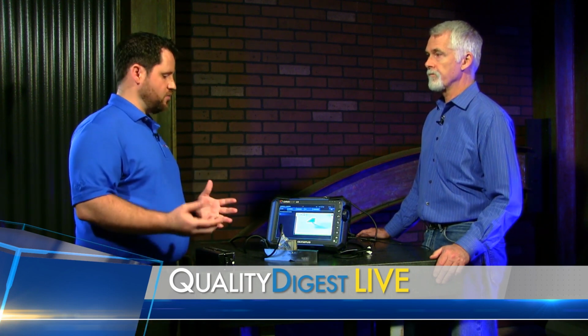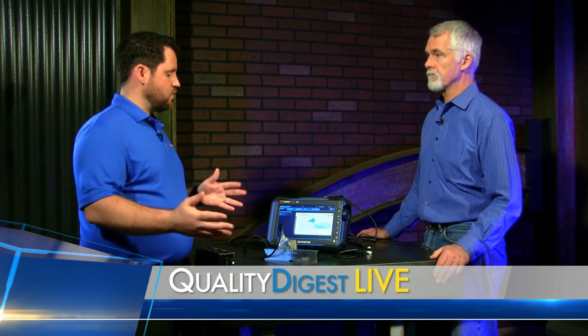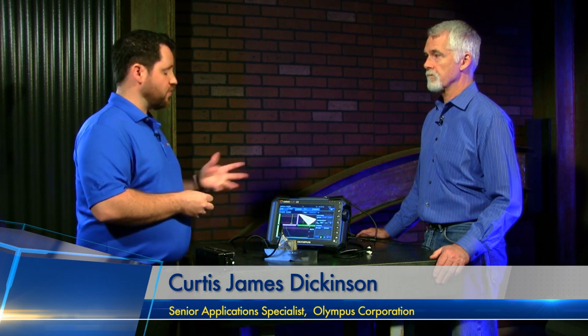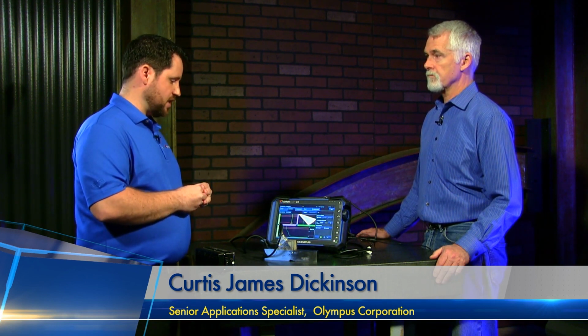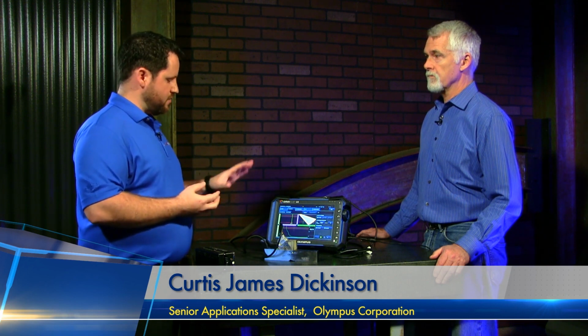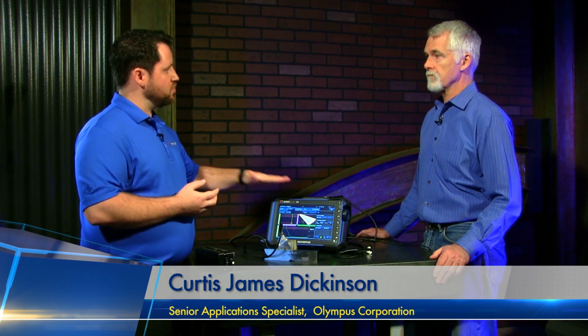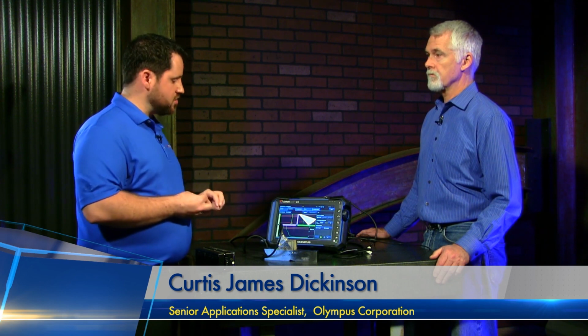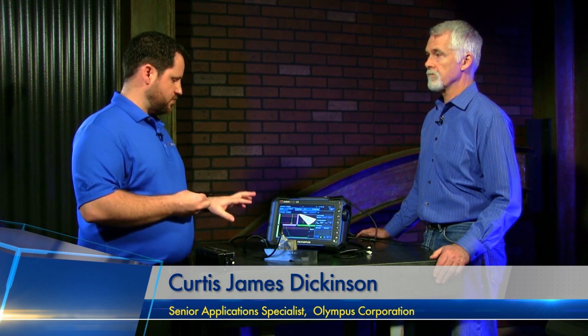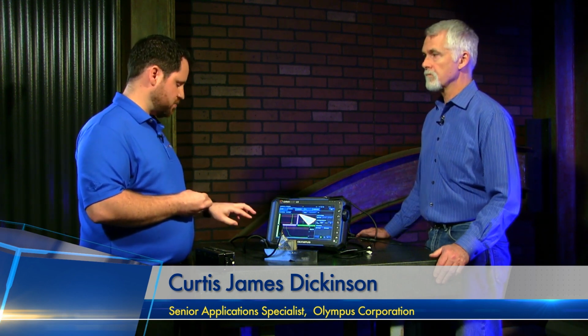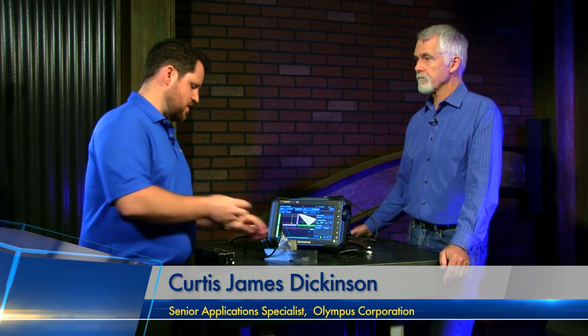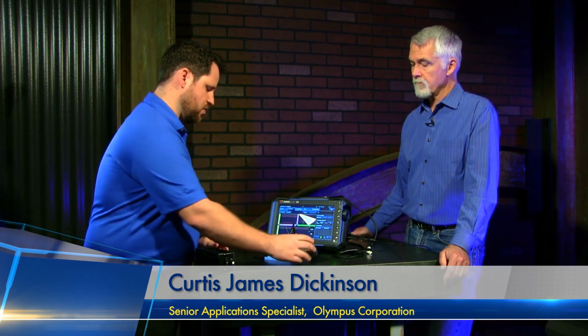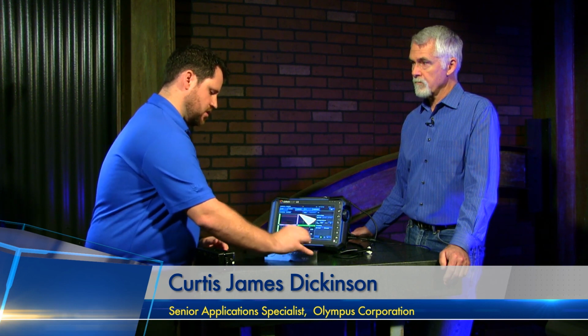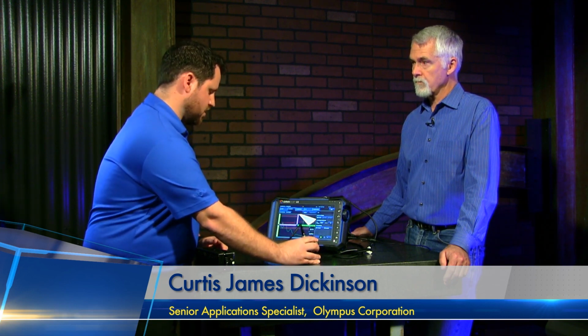So typically the operator would perform their setup, adjust all the parameters, and then come back through and perform one of the calibrations for the unit, which we've also tried to improve on a little bit and make it easier for the technician. Have all of the calibration options in one place, make them a little bit easier to work through in terms of how much information is on the display, on the screen, and then just really try to improve upon the overall performance of those calibrations.